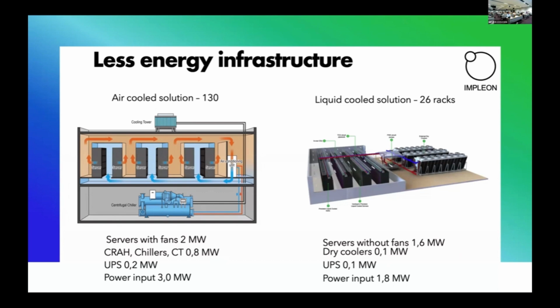On this slide, I show that servers without fans will use less energy consumption. Also, the density per rack can be much higher with liquid cooled. Comparing the same amount of CPUs and GPUs between the two solutions, the rack quantity is less, the power for IT is less, and the temperature is higher for liquid cooling.